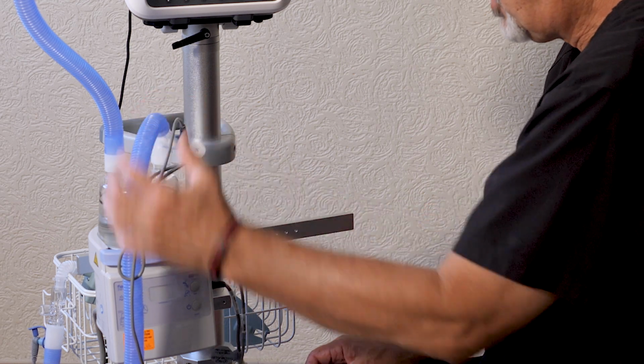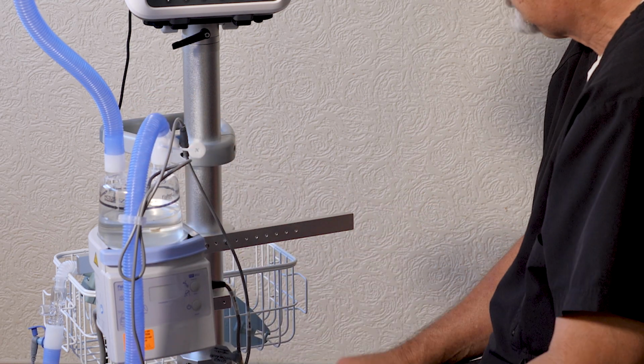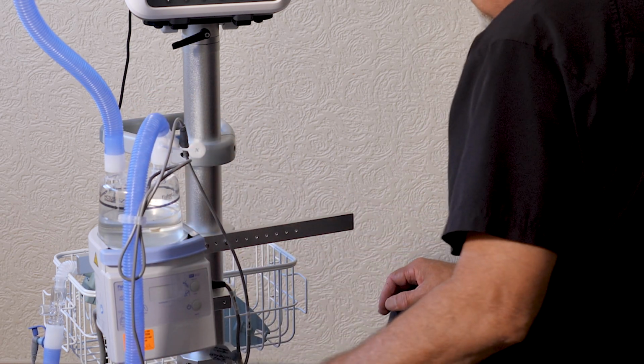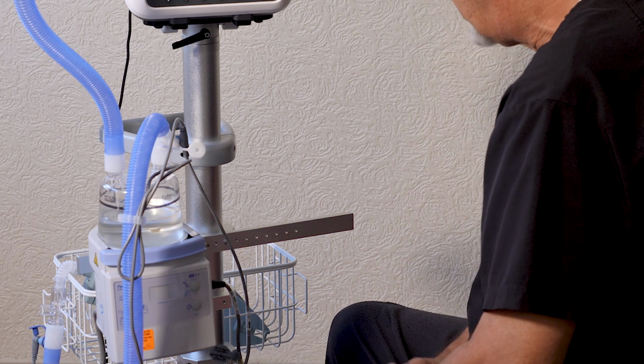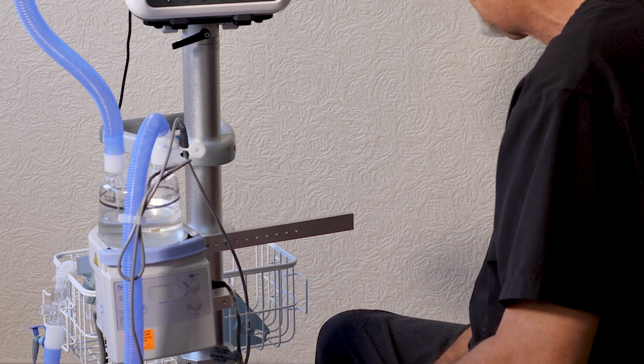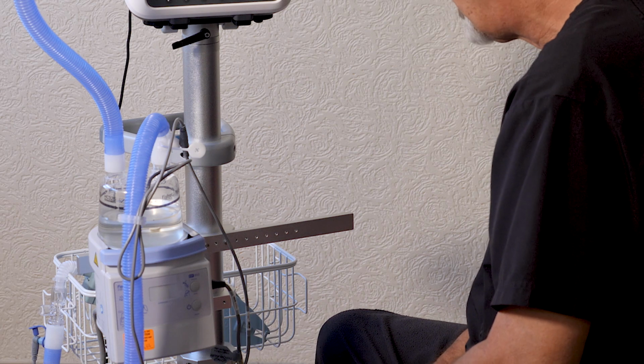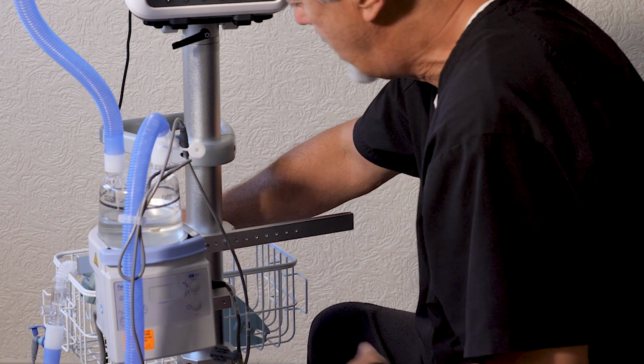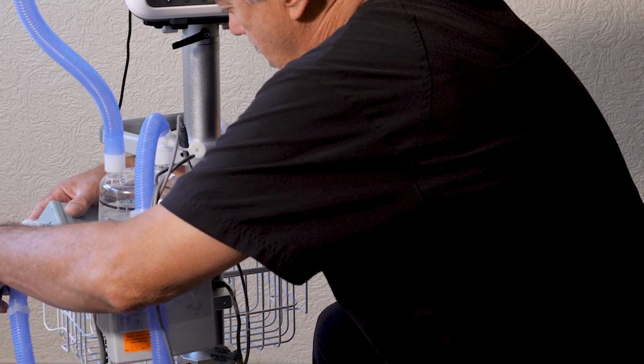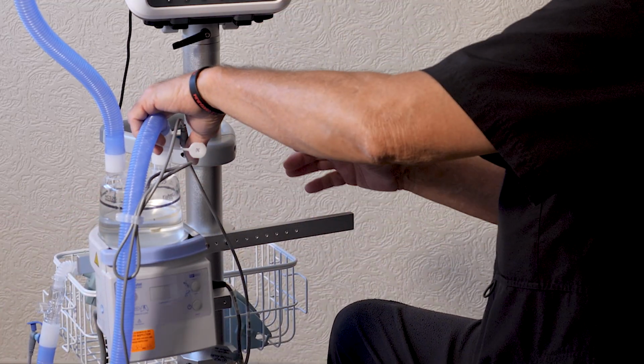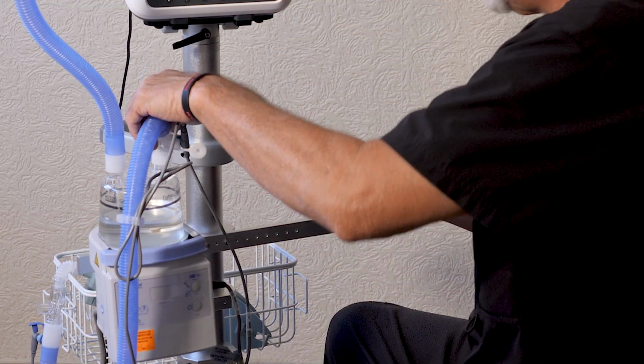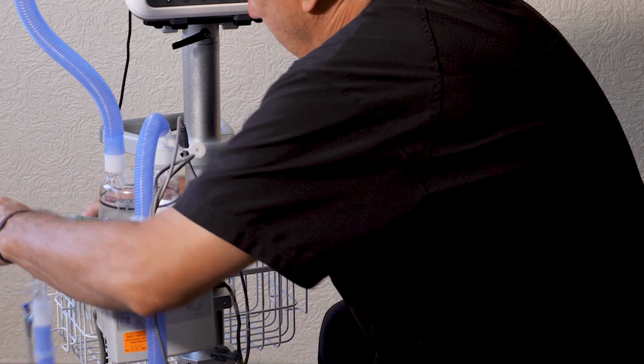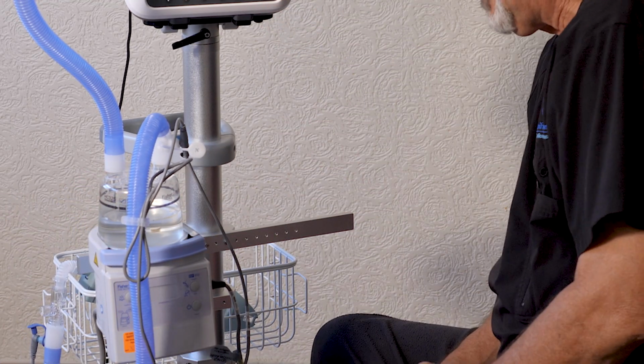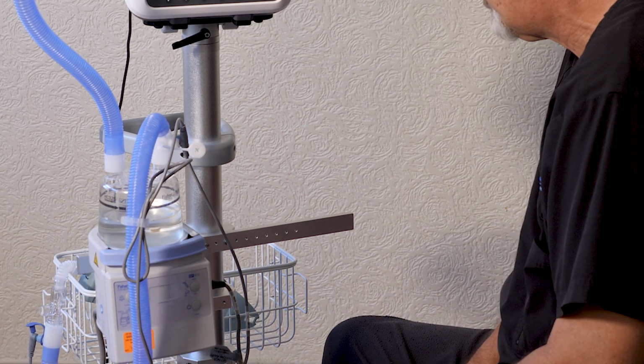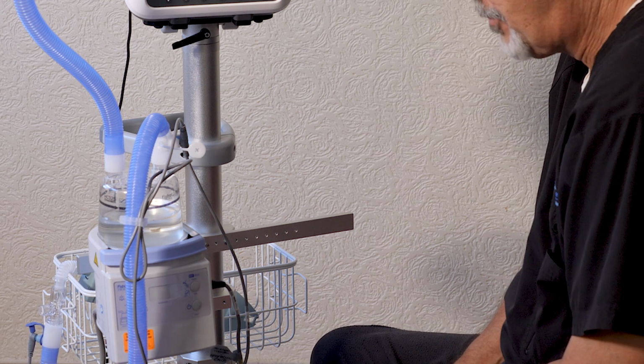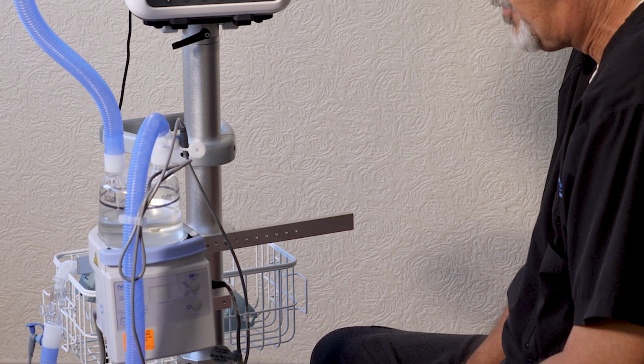So you get the new part of this circuit out, you have it ready to go. And again, if the patient cannot be off the ventilator for very long, have somebody stand by with an ambu bag. If the patient can be off for a minute or so, then it's very easy to do. You just basically disconnect this part of the circuit from the patient, disconnect this part here, and then bring the new circuit, reconnect it to here, and then reconnect it back to the patient. That way, the patient is without being ventilated for a short period of time, probably 5 seconds at the most.